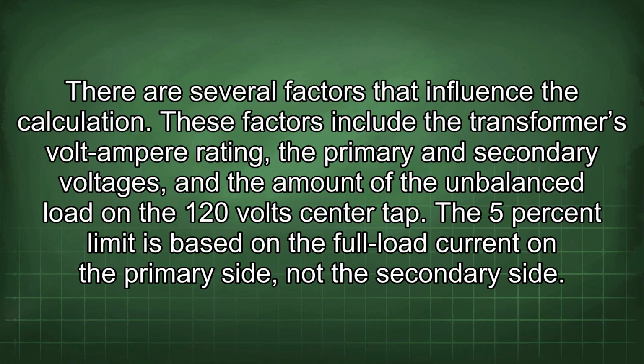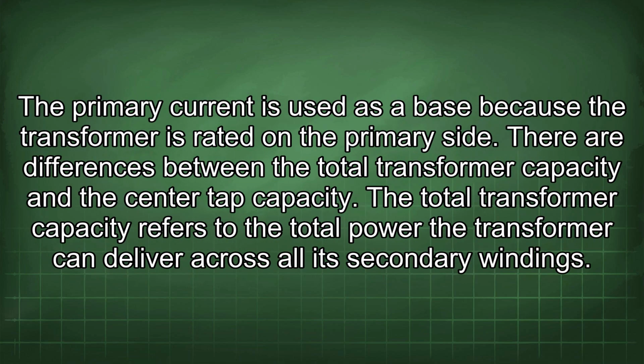There are several factors that influence the calculation. These factors include the transformer's volt-ampere rating, the primary and secondary voltages, and the amount of the unbalanced load on the 120 volt center tap. The 5% limit is based on the full load current on the primary side, not the secondary side. The primary current is used as a base because the transformer is rated on the primary side.